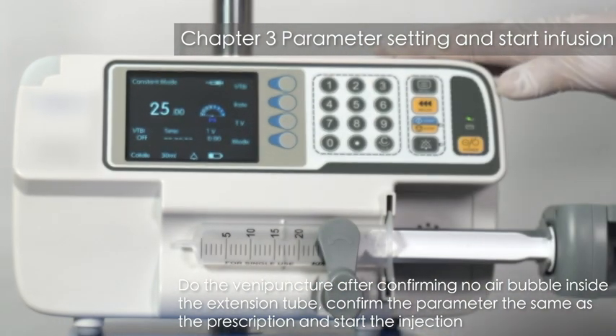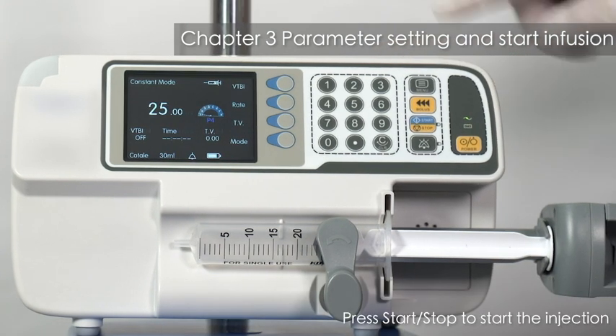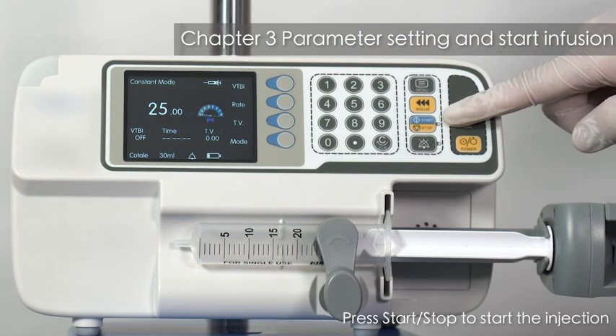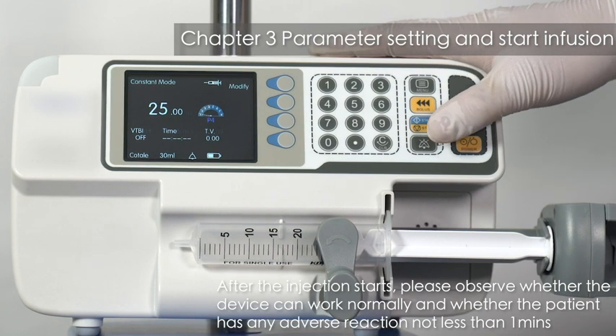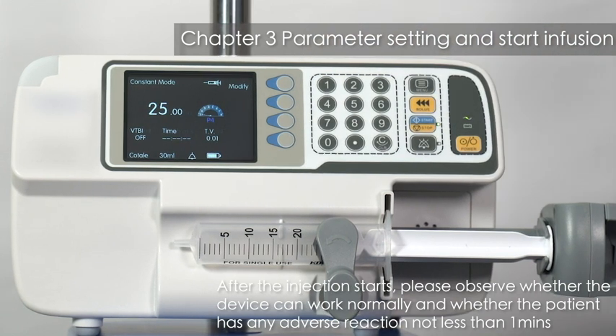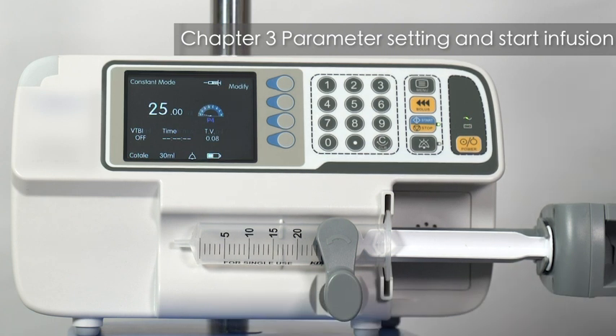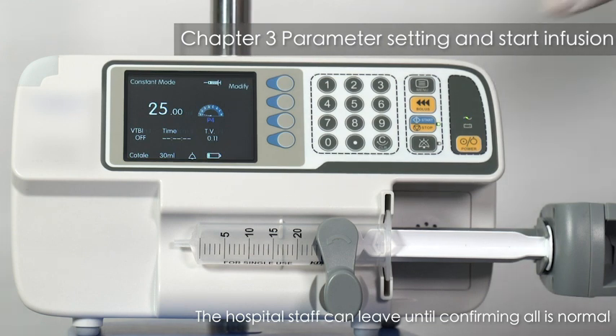Confirm the parameter is the same as the prescription and start the injection. Press Start, Stop to start the injection. After the injection starts, please observe whether the device can work normally and whether the patient has any adverse reaction, not less than 1 minute. The hospital staff can leave until confirming all is normal.